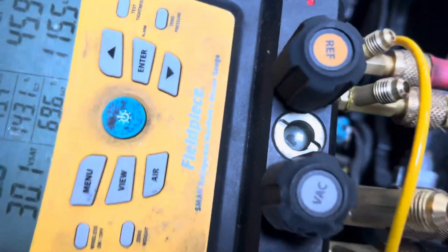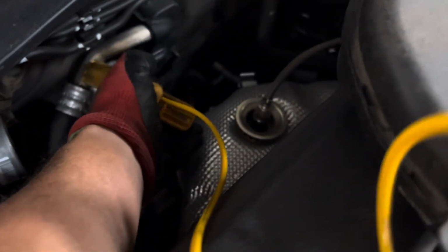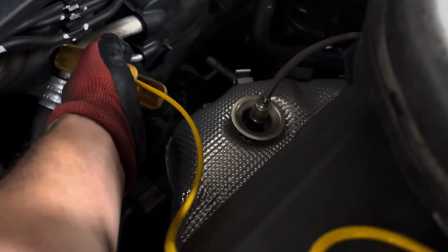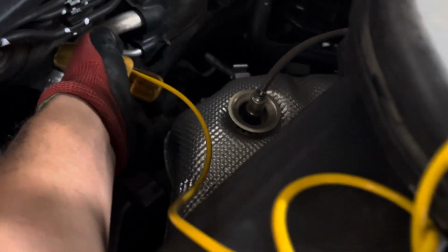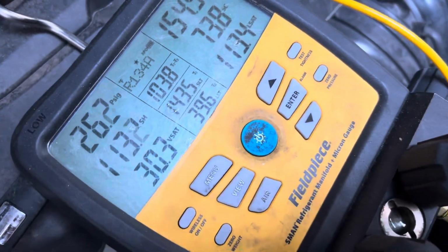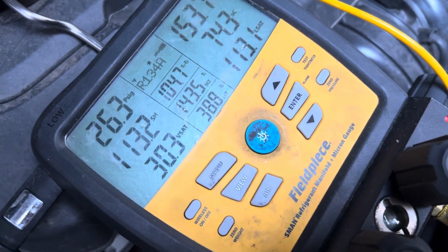We're taking it off of there, and now we're going to put it before, right there. Now we're grabbing on to the same suction line, but we are before the internal heat exchanger. Now look at the temperature. 39 degrees, 38 degrees.